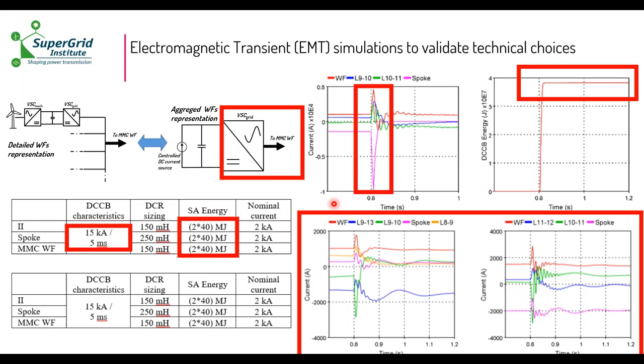A busbar topology assessment allows you to choose cost-effective topologies, let's say, what you need for the specific protection need of the grid. So you don't oversize all the time and put breakers everywhere. This is a technical perspective for future work: if you can be more precise on what the AC constraints are, because here we use the grid codes and what people are already used to due to the normativity in AC. But if you can study better and be more precise on the AC constraints, maybe you can be even more cost effective and reduce some of the AC constraints to allow non-selective fault clearing strategies to be considered at some points of the system.